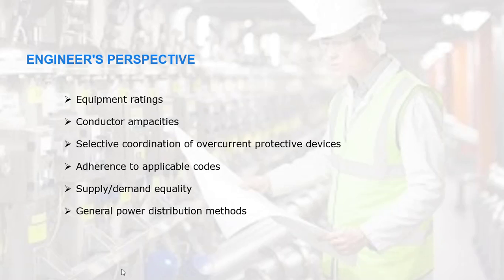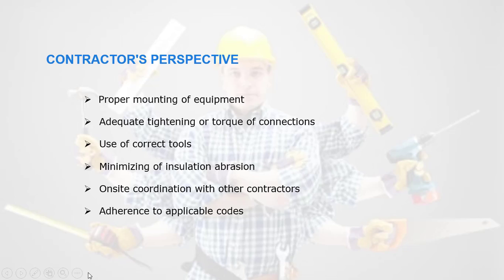Engineer perspective: equipment rating, conductor ampacities, selective coordination of overcurrent protective devices, adherence to applicable codes, supply demand equality, general power distribution methods. Contractor perspective: proper mounting of equipment, adequate tightening or torque of connections, use of correct tools, minimizing insulation abrasion, on-site coordination with other contractors, adherence to applicable codes.